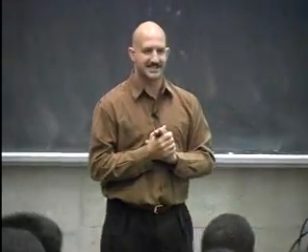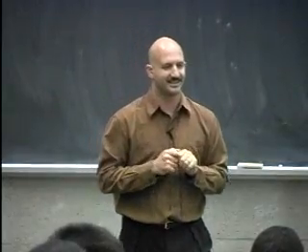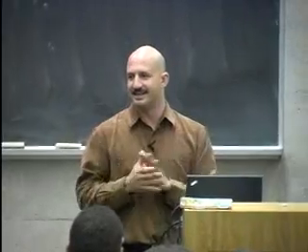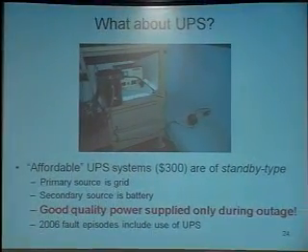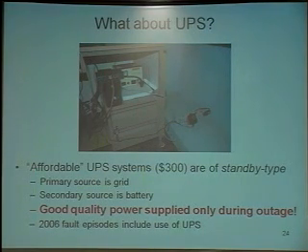Well, all the problems I just told you about were with a UPS in place. We didn't forget the UPS. We used the UPS. And this is a bit surprising because a UPS is supposed to fix this problem, and it doesn't, at least at the price range we're talking about. Higher-end UPSs can fix this. A low-cost UPS is a standby UPS.